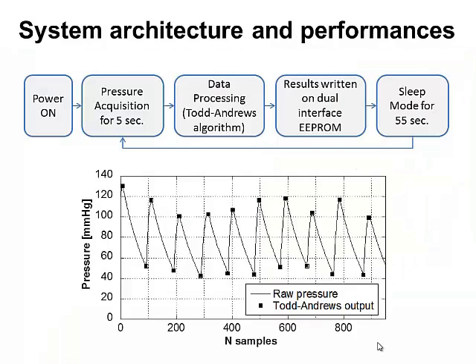Okay, as concerns the system architecture, we programmed the firmware of this platform in order to do pressure acquisitions for 5 seconds, which corresponds to a few cardiac cycles, and then to process this data in order to find the maximum, minimum, and the average pressure with the Todd Andrews algorithm. And here you can see the validation of the algorithm, manually varying the pressure at the entrance of the sensor. You can see that all peaks are detected in a nice way. This algorithm is, let's say, immune to baseline wandering, which is an important feature.